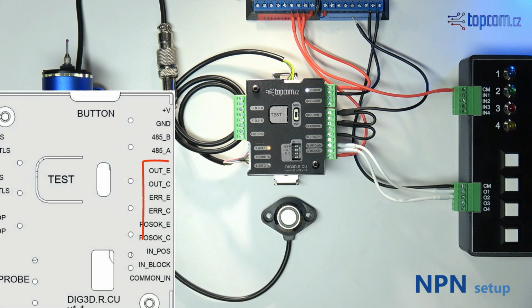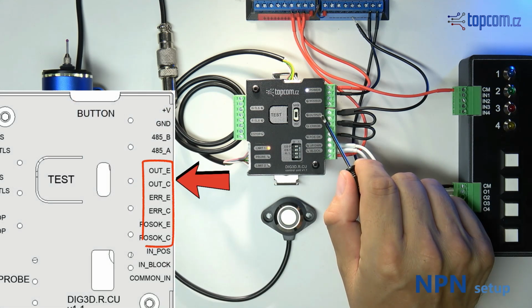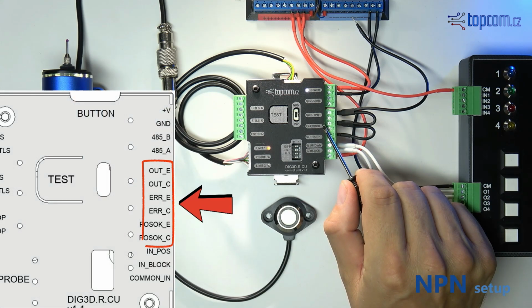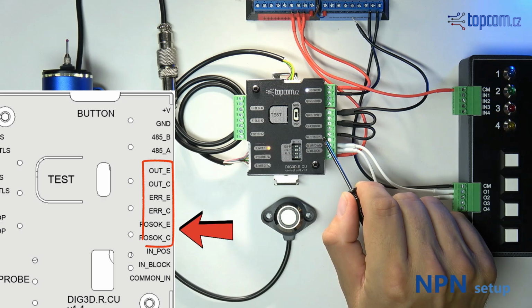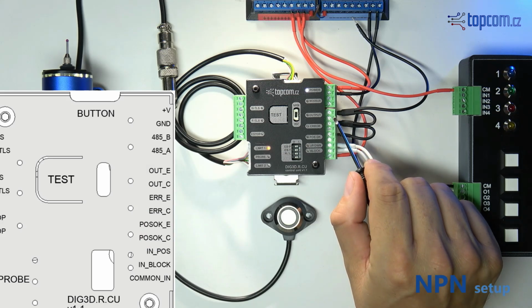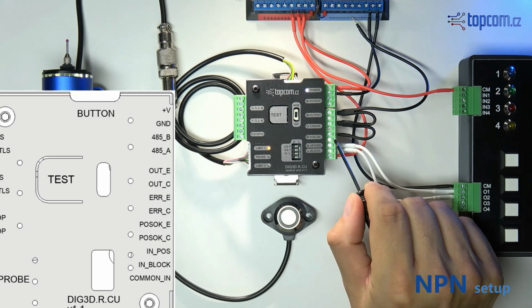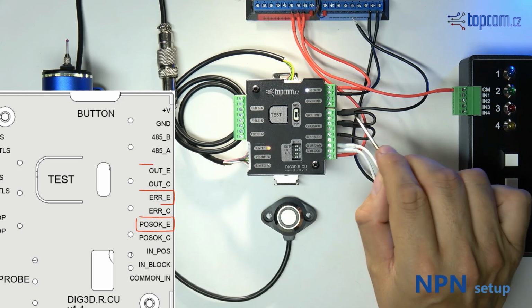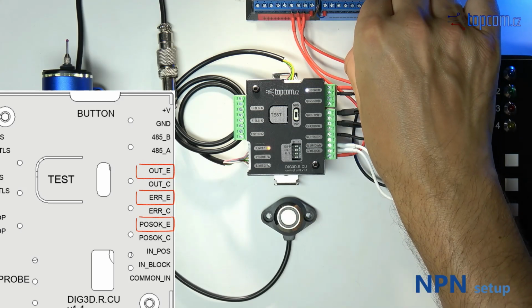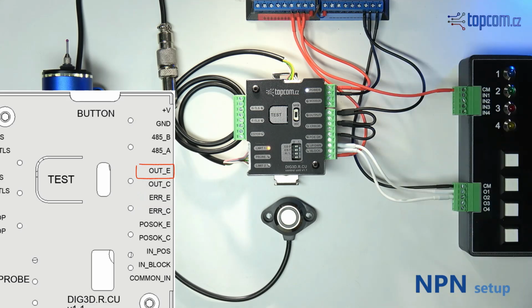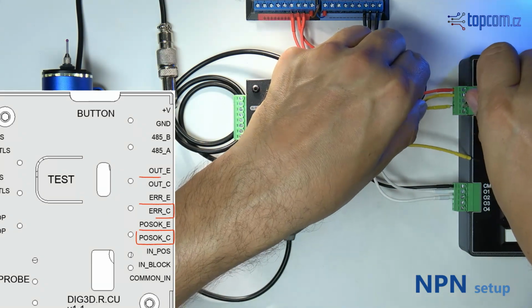The control unit provides 3 outputs: a combined signal output from the probes, an error output, and a position reached output. Each output occupies 1 terminal pair. In an NPN configuration, all terminals labeled E are connected to the negative pole of the power supply. The terminals labeled C can now be connected to the inputs of the motion control board.